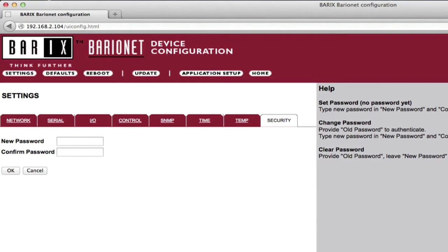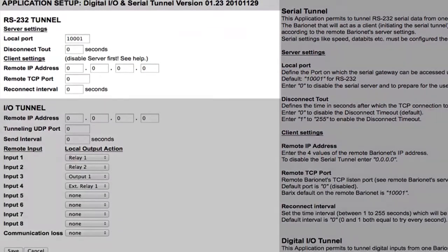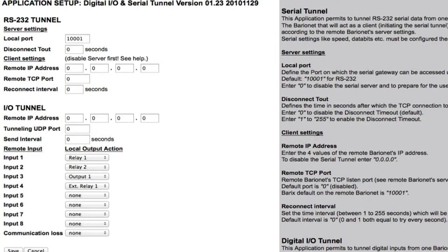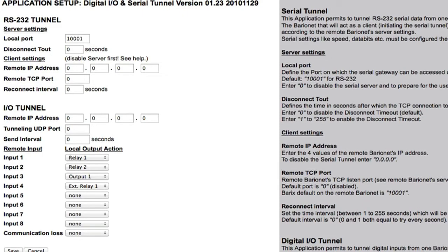The Baryonet comes preloaded with a sample BCL application that supports two tunneling functions. First, it allows bi-directional tunneling of one Baryonet's serial data across the network to and from a second Baryonet's serial port using TCP. The application also allows two Baryonet 100s or Baryonet 50s to tunnel one's inputs to another's outputs using UDP. The I/O Tunnel application also supports connecting an external Baryonet R6 relay expansion module to one or both Baryonets via the RS-485 port.